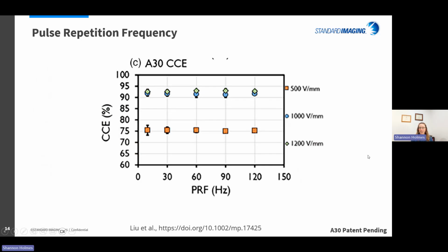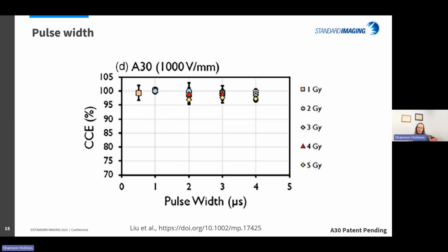So going on then with that A30 design with the smaller diameter collecting electrode, we looked at pulse repetition frequency, and at these higher electric field strengths, we get a nice uniform response across a good range of pulse repetition frequency for these high dose per pulse electron beams. We looked at pulse width as well, because the width of the pulse for a certain dose will also impact the response of the chamber. And again, we got good matching with our theoretical model's results across a range of pulse widths. Up to 4 microseconds was the largest we're looking at, and up to 5 gray. We can't get that in the small pulse widths, but up to 5 gray per pulse with these narrow pulse widths, the chamber was performing beautifully, again, at that 1,000 volts per millimeter electric field strength.